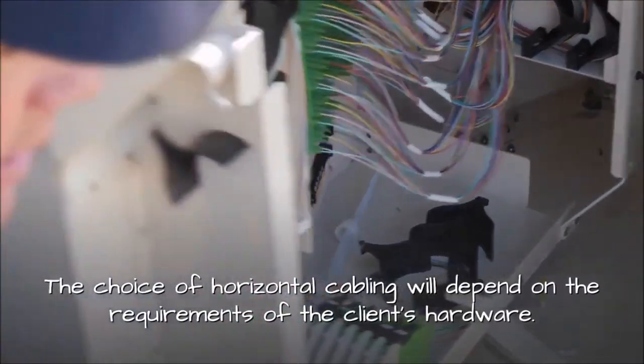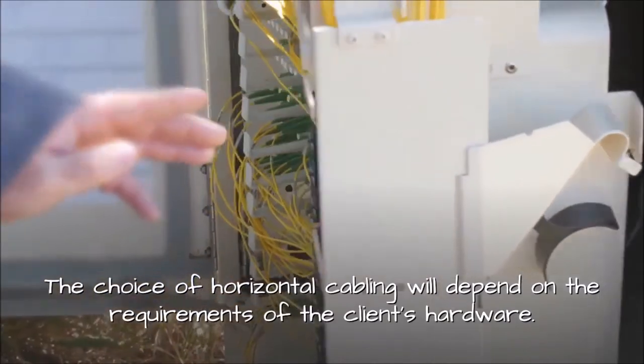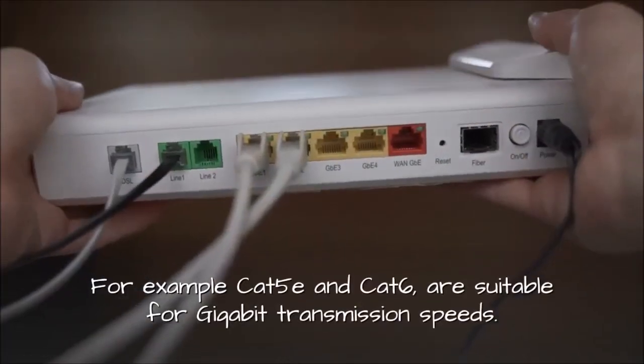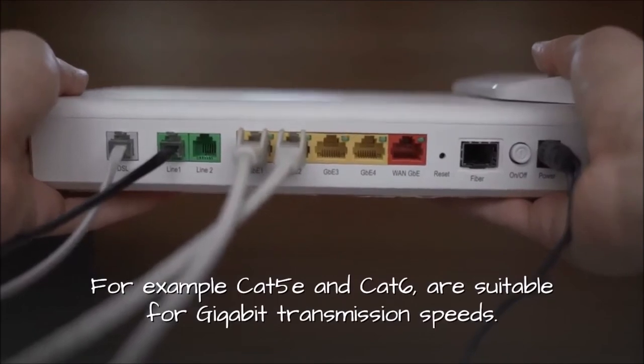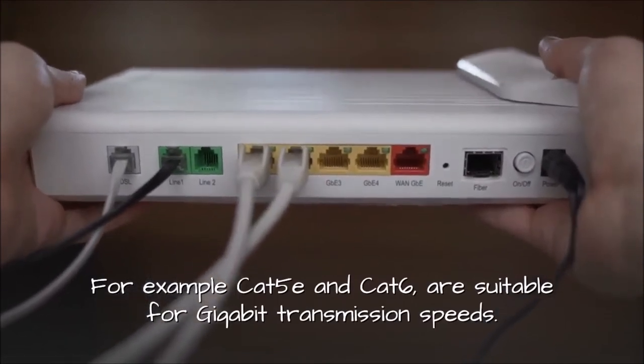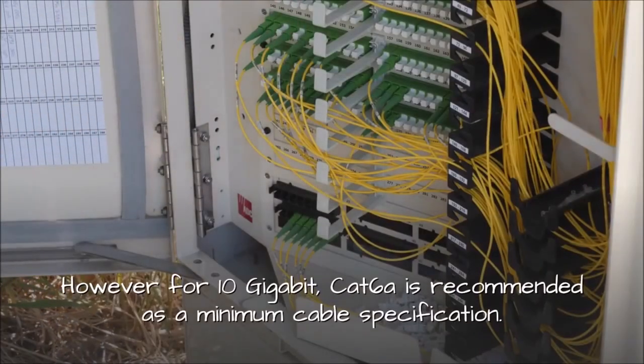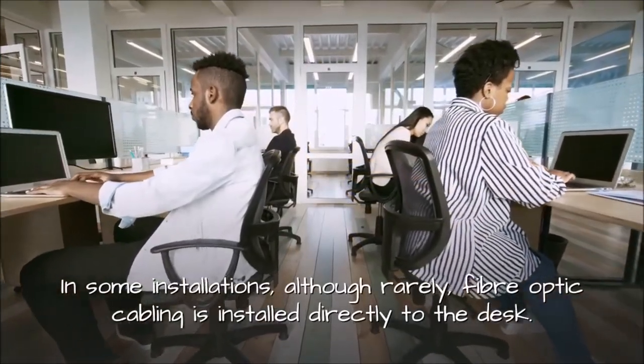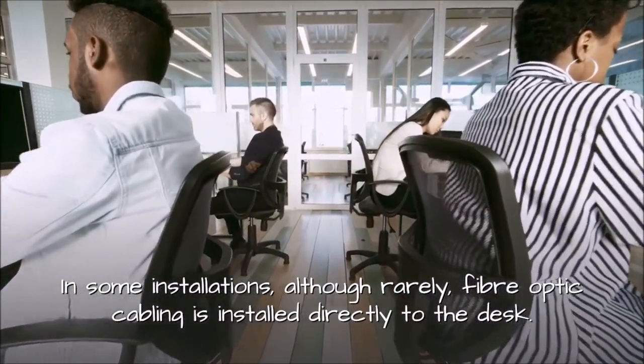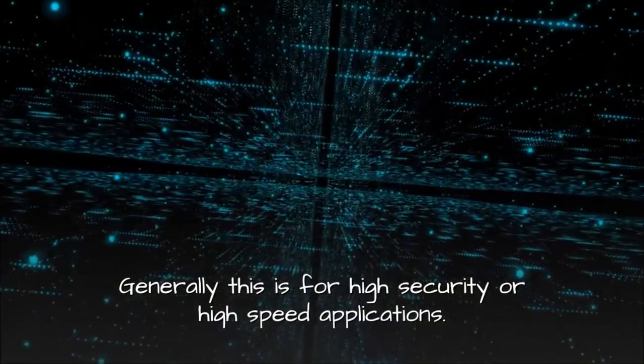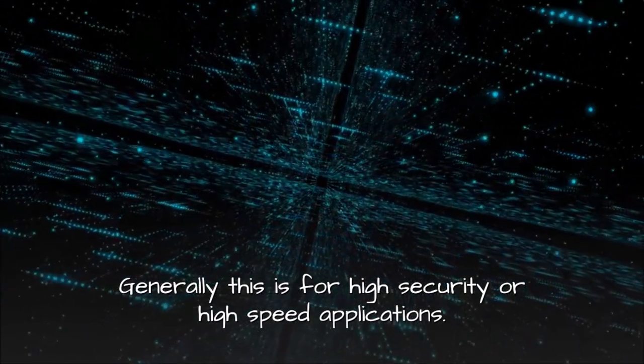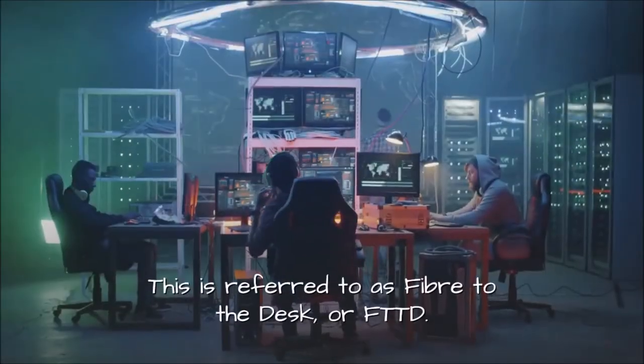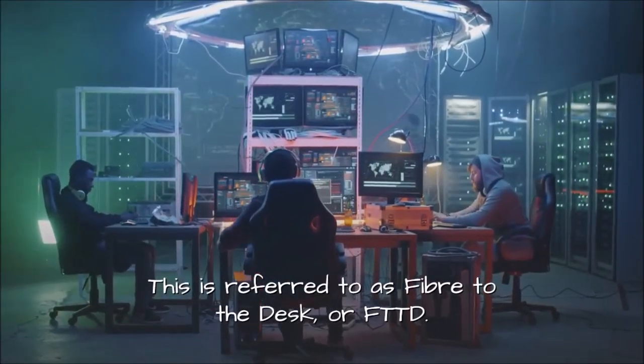The choice of horizontal cabling will depend on the requirements of the client's hardware. For example, CAT 5e and CAT 6 are suitable for gigabit transmission speeds. However, for 10 gigabit, CAT 6a is recommended as a minimum cable specification. In some installations, although rarely, fiber optic cabling is installed directly to the desk. Generally this is for high security or high speed applications. This is referred to as fiber to the desk, or FTTD.